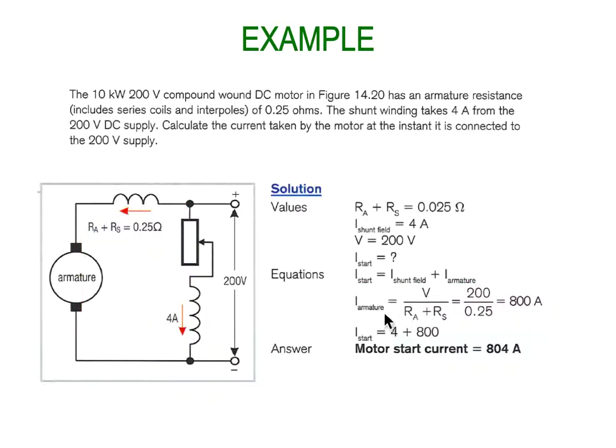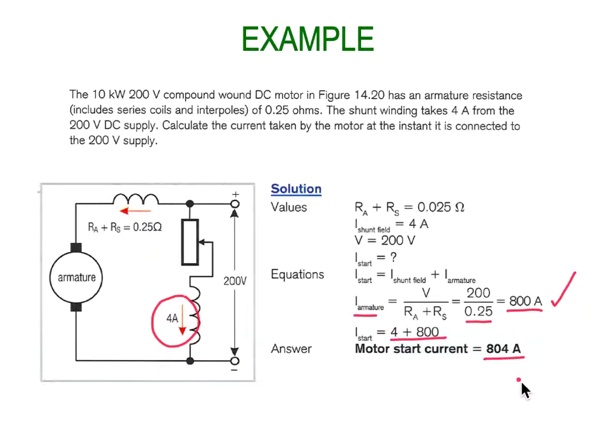The armature current is reasonably easy to work out — it's simply the voltage divided by the resistance. So 200 divided by 0.25 is 800 amps, which is the vast majority of the current. Our shunt field separately is 4 amps independently, and we end up adding those together. The correct answer is 800 amps. So to get a motor up and running — just this 10 kilowatt motor, which is not a huge motor — takes 800 amps at start, before any back EMF is initialized and reduces our current. That's going to take a fair bit of thinking about.